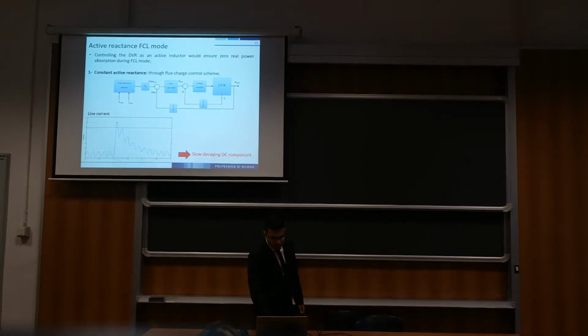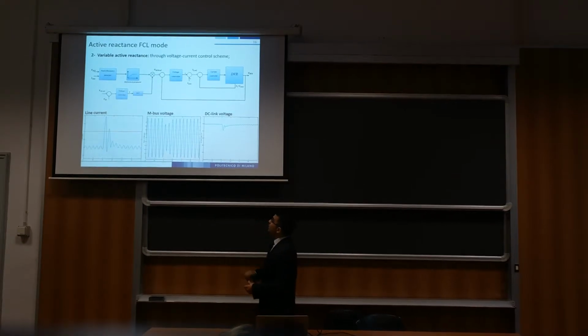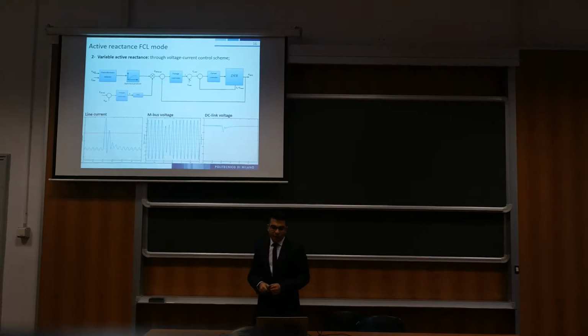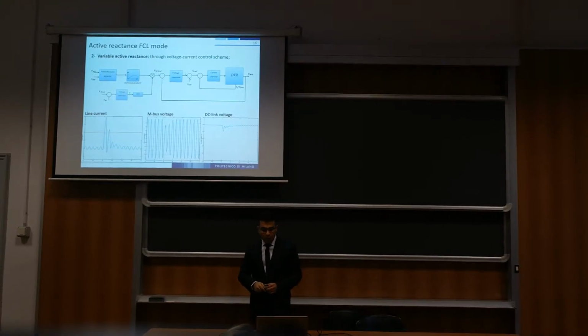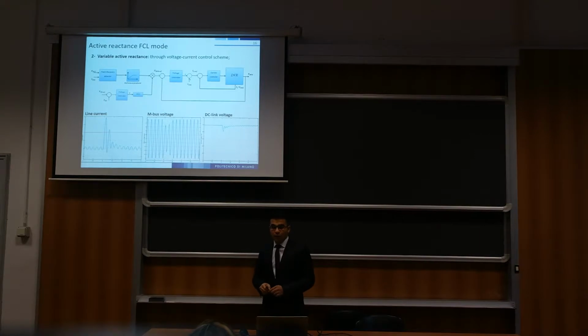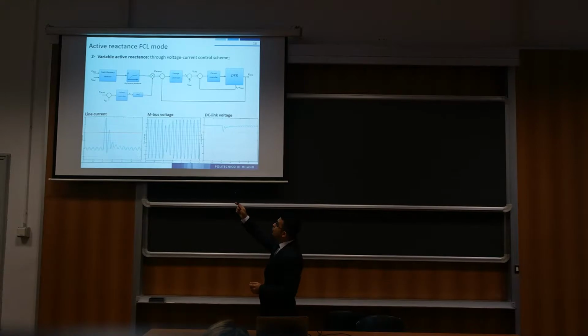For solving this problem, I have proposed this strategy, which is based on variable active reactance using voltage current control scheme. This strategy is based on increasing the voltage of a DVR in a ramp form instead of a step injection. Also, it should be noted that even during pure active inductance injection, DC link voltage would drop because of DVR losses. In order to avoid this drop and have a constant DC link voltage, the phase of the injection voltage is supposed to be constructed using a DC link voltage controller.